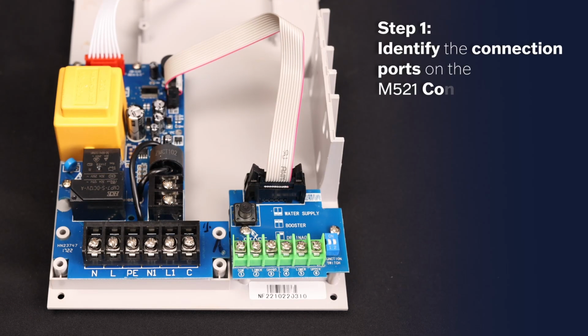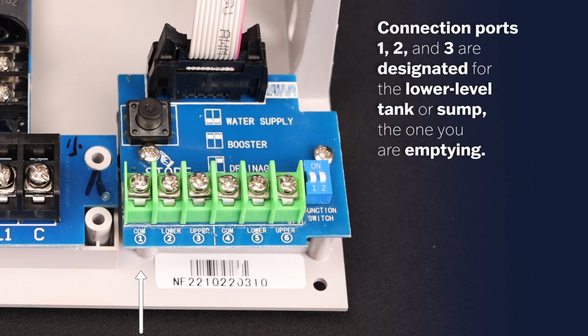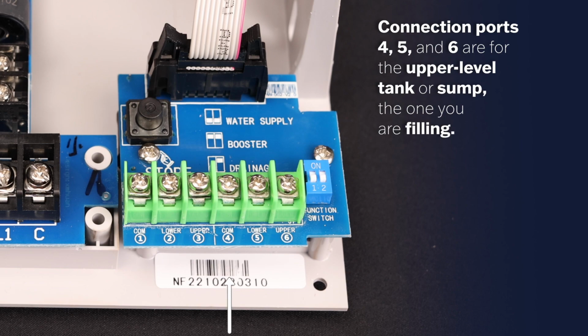Let's get started. Step 1. Identify the connection ports on the M521 controller. Connection ports 1, 2 and 3 are designated for the lower level tank or sump, the one you are emptying. Connection ports 4, 5 and 6 are for the upper level tank or sump, the one you are filling.